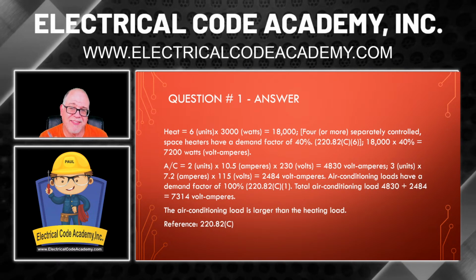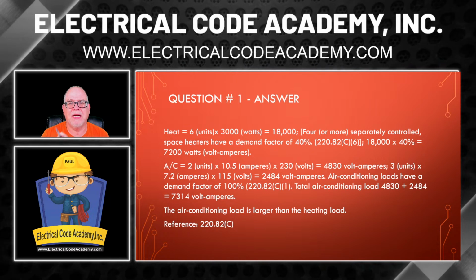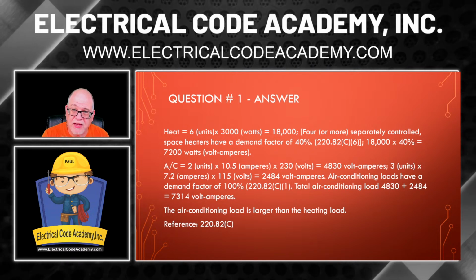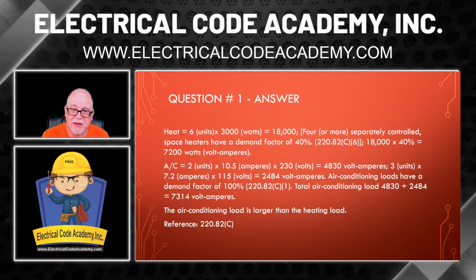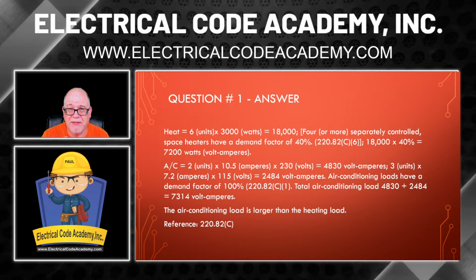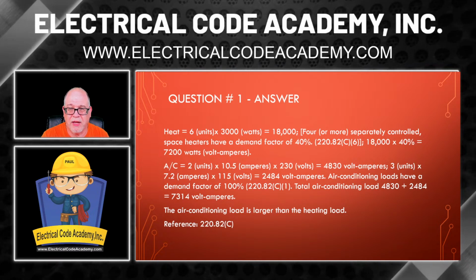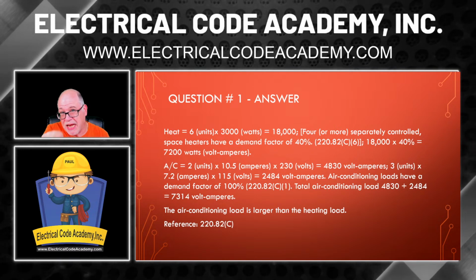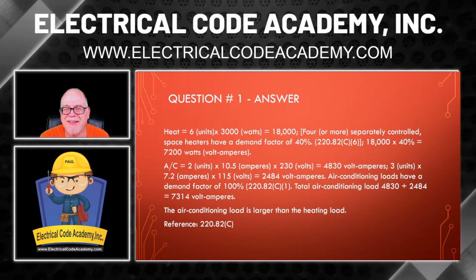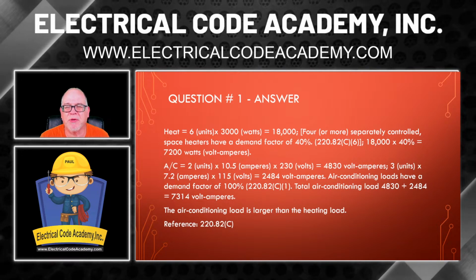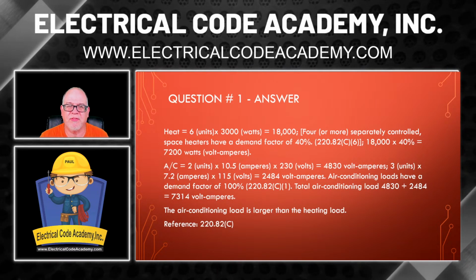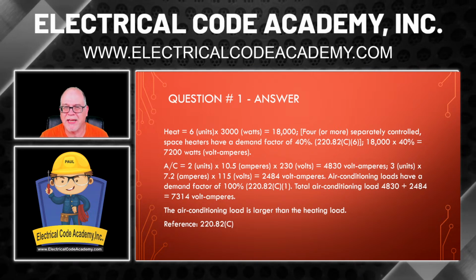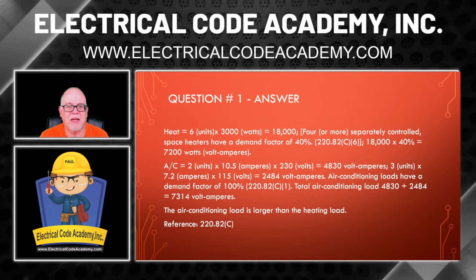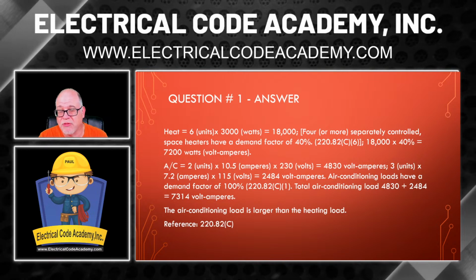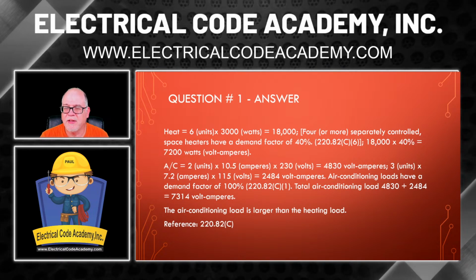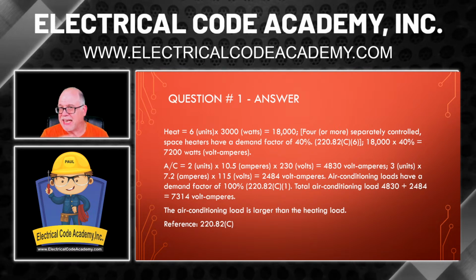Now, remember what it said? It says that we take what? Now, this says 220.82(C)(6), but it's actually, which one was it? It was (5) that we're using for the heat. So, typo. So we're doing 18,000, and we're going to multiply that by 40%. That gives us 7.2 kW, or in our case, since we worked it out in watts, it is 7,200 watts, or 7,200 VA.